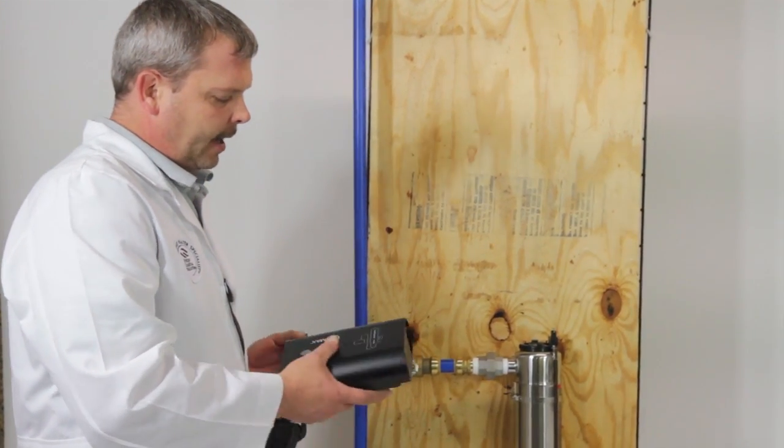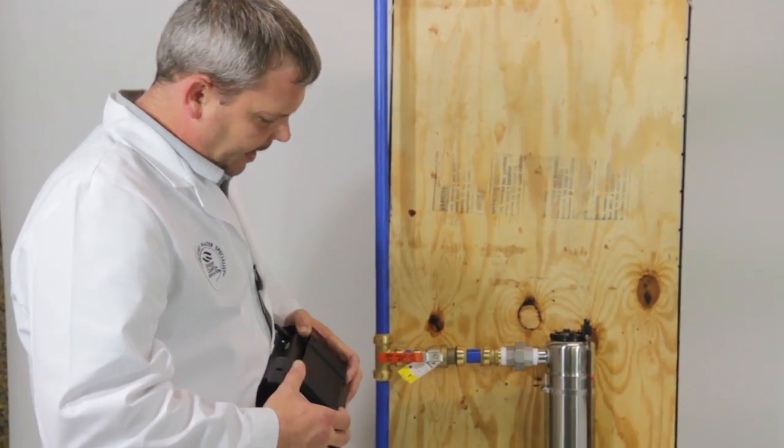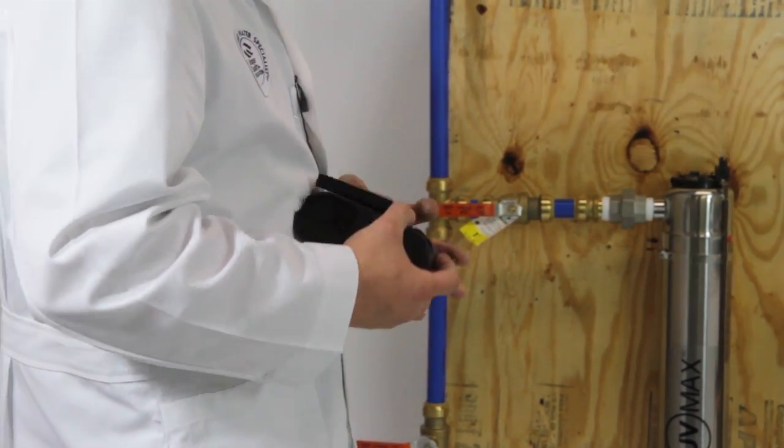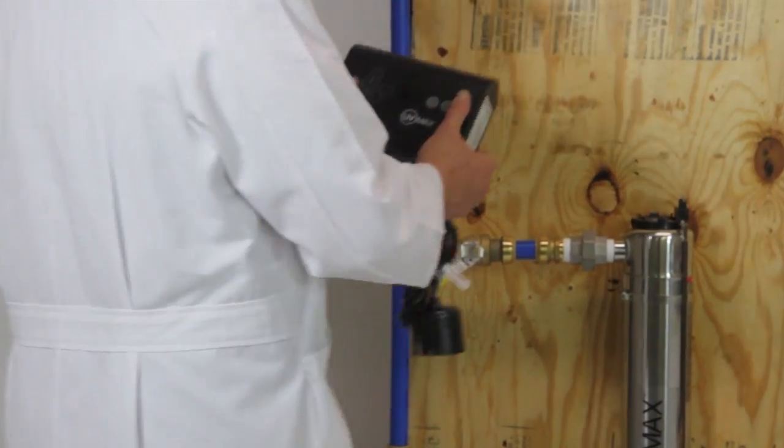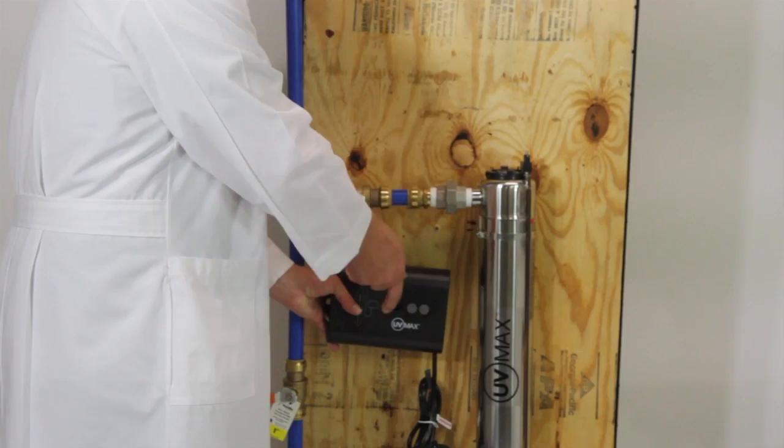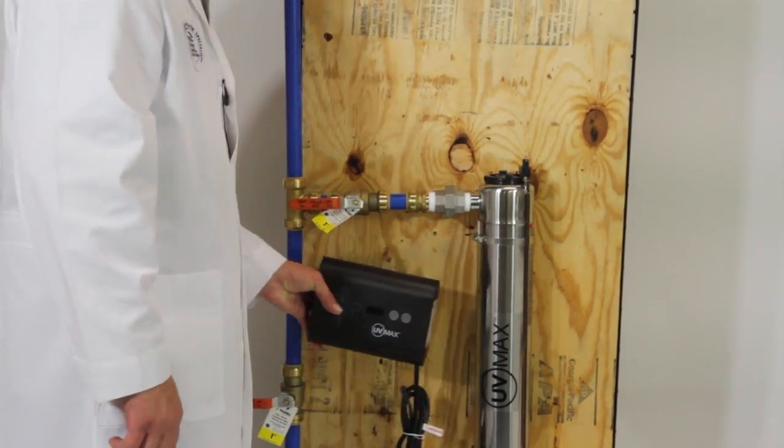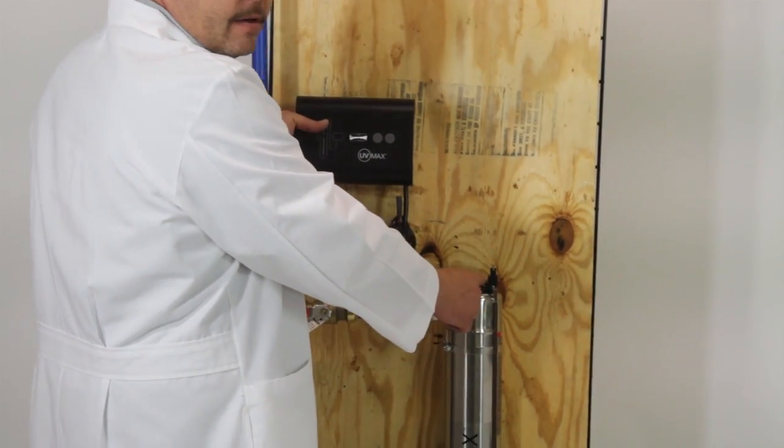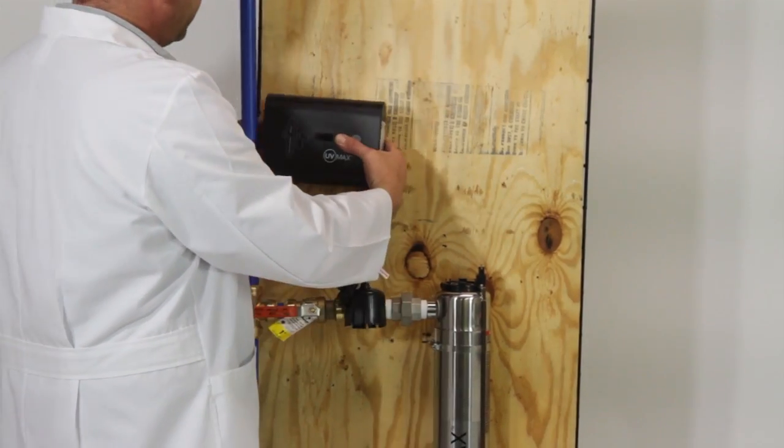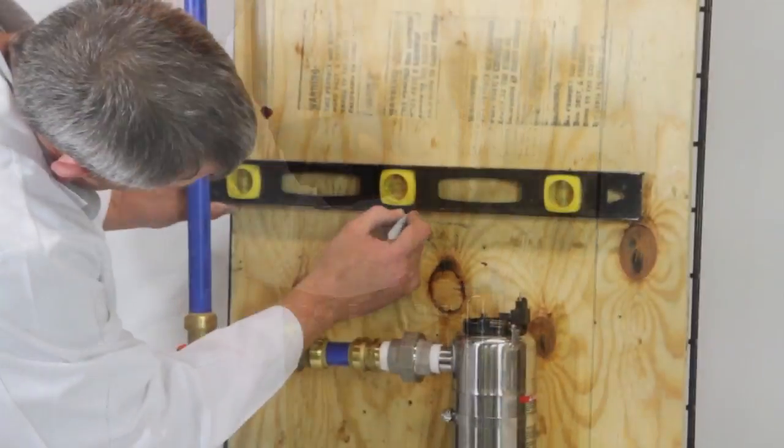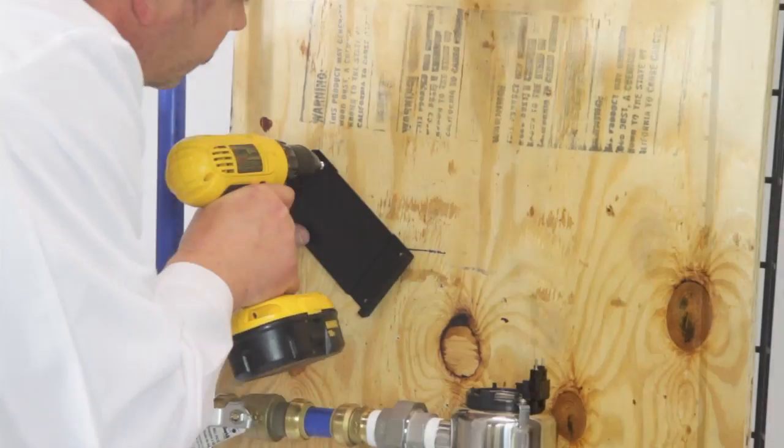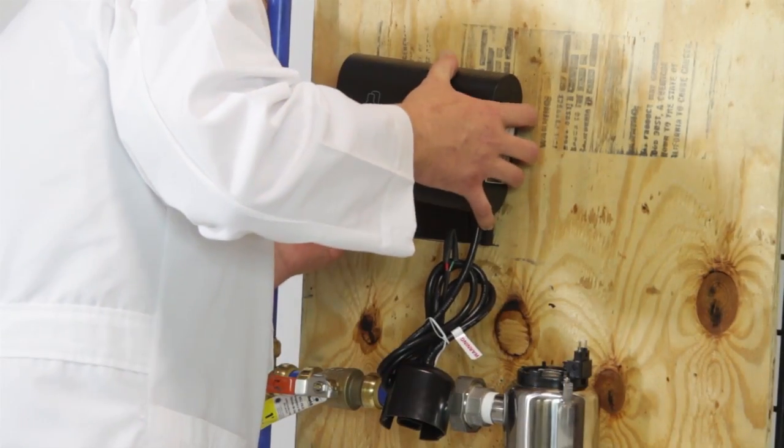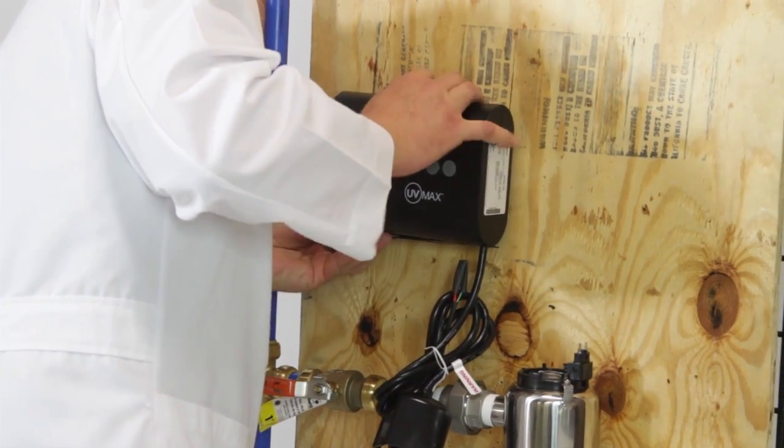Once we have the plumbing complete and we have everything secured and tight, then we're going to mount our ballast. It has a bracket that will slide off that we're going to mount to the wall. We don't want this down low because if anything drips, it leaks on it and burns up the ballast. We want it above the plumbing as much as possible, but we don't want to put it over top of the bulb chamber so we can't get the bulb out. For this application, I'm going to mount it basically right up in here. You can use a level and your proper fasteners to mount this actual bracket. Once your bracket is mounted, you can slide your ballast into the bracket and it's securely mounted to the wall.